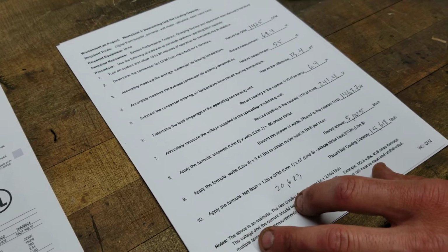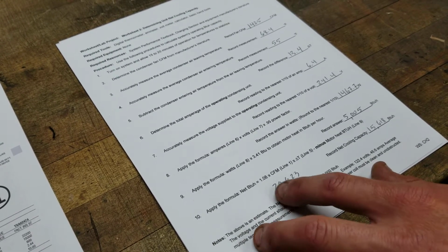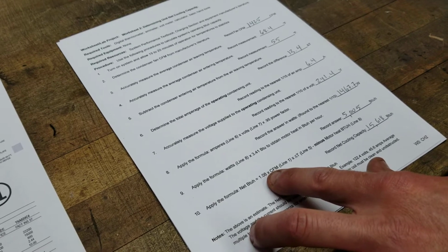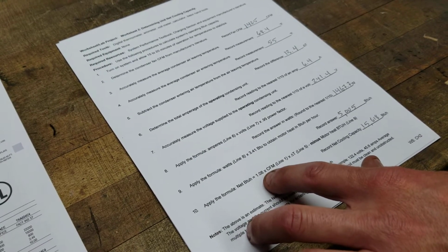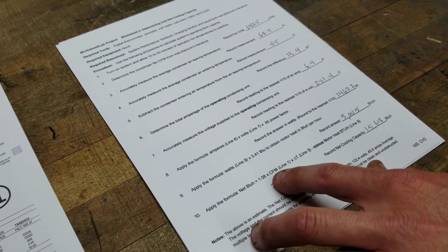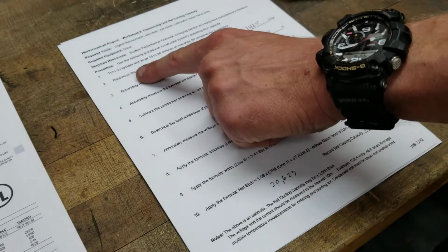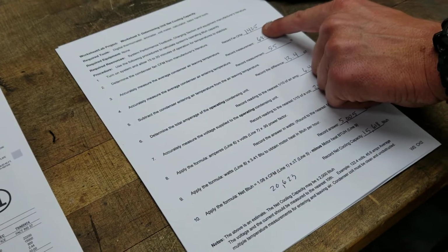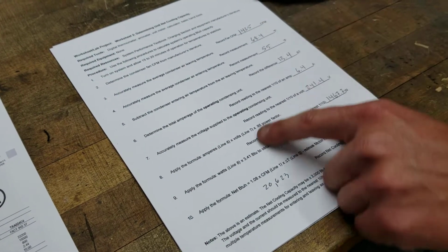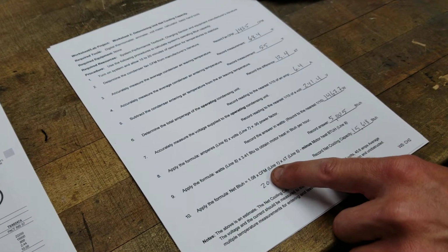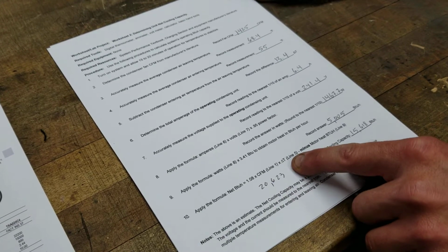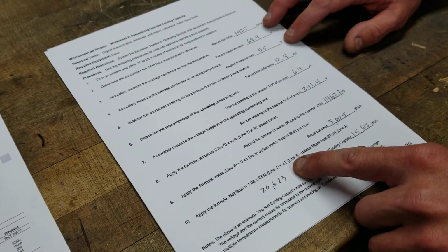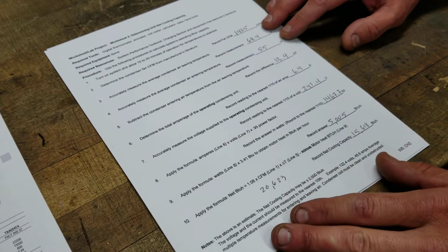And our air density at sea level, that's where, going back, oh God, probably about 10 weeks now, that number comes from. So we got our constant times our CFM, which we get from a manufacturer online, 1425. That's our CFM of our outdoor fan motor, times our delta T, which we measured, is the condenser split, some call it.